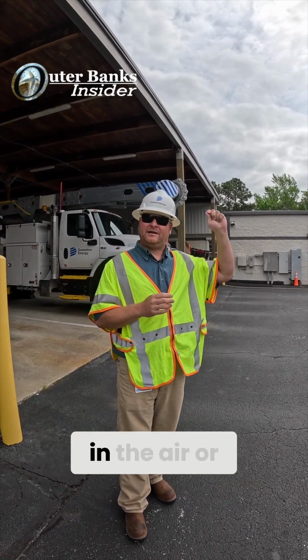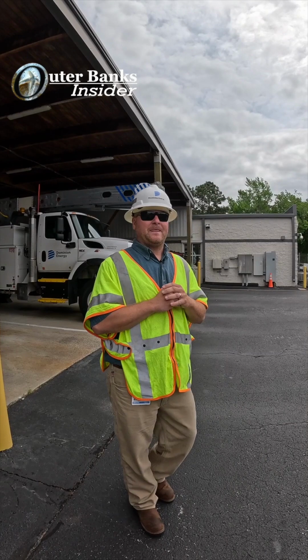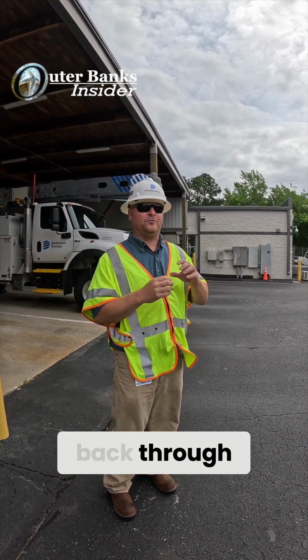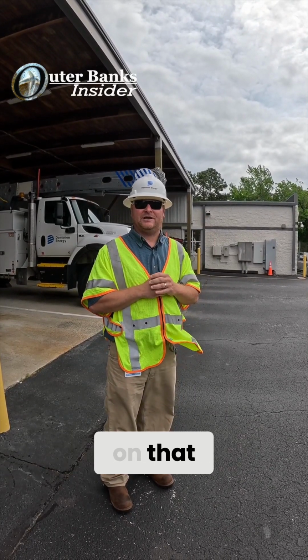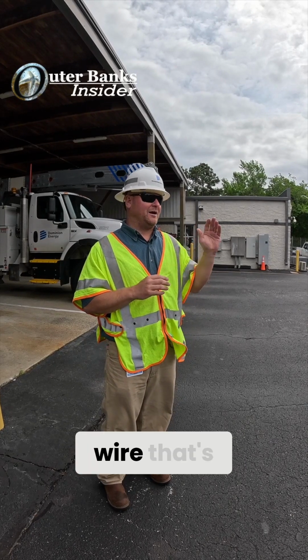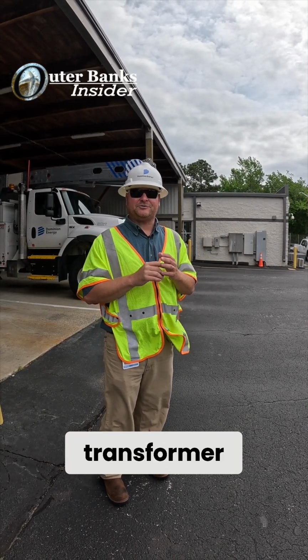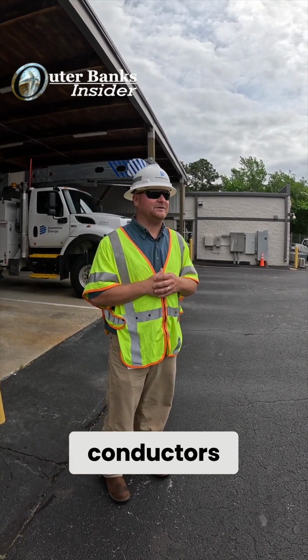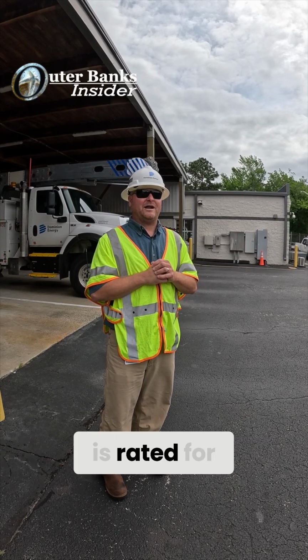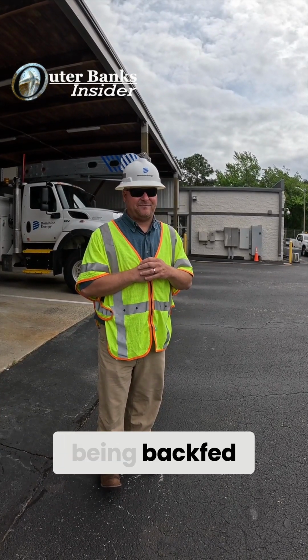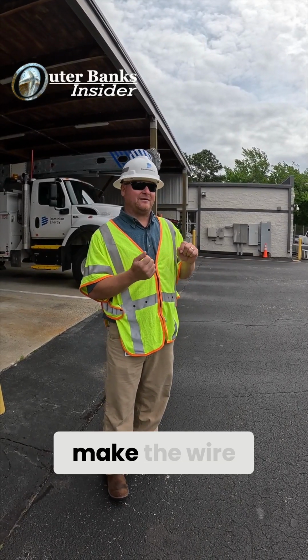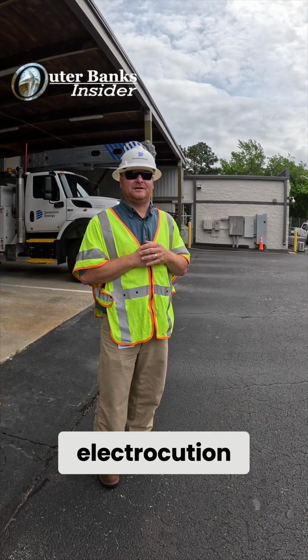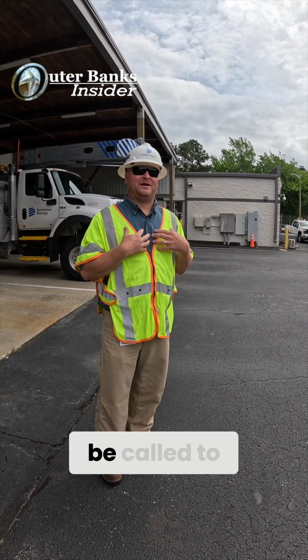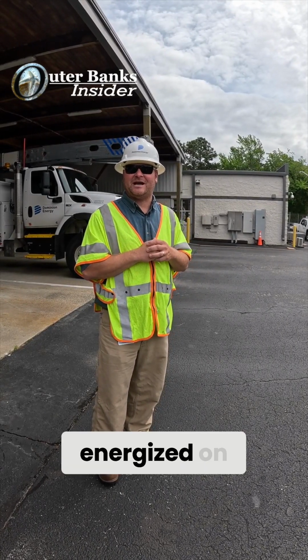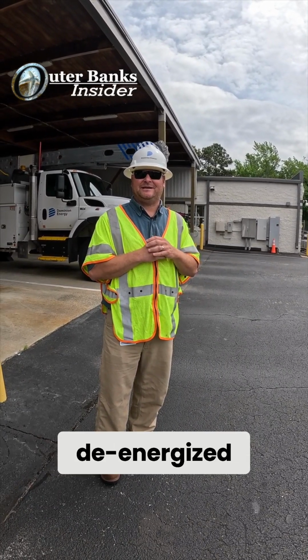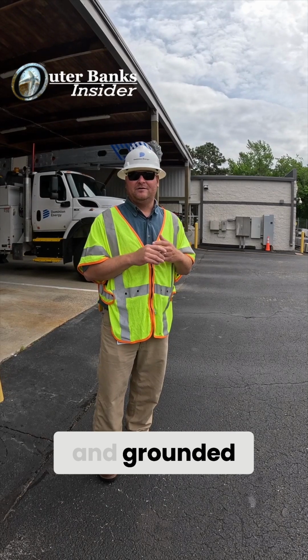Our transformers, either in the air or underground, will produce voltage back through the secondary windings and out the primary side of the transformer. That can create voltage on a wire that's down on the ground. If a transformer is rated for 19,000 volts, and it is backfed through the secondary windings from a generator, it can make the wire laying on the ground carry that voltage. That can lead to electrocution. We're the professionals out there, so we need to be called to make sure that line is not energized on the ground. A line is not considered de-energized until it's properly tagged, tested, and grounded by one of our line workers.